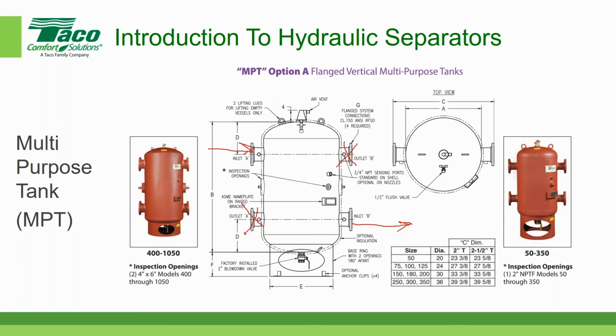It's not until you put all 4 connections in here that you create, as it's shown in this diagram, the inlet primary here and the outlet for the primary side, and then the outlet for the secondary side and the inlet for the secondary side. It's not until you have these connections in that configuration that it becomes a hydraulic separator. You answered that one, my friend.